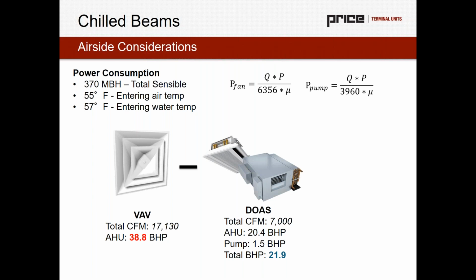When we're looking at the airside considerations for this equipment, I just want to paint it a little bit more. This is a case study that our beam team put together, looking at an open office environment providing 370 MBH of total sensible cooling with 55°F entering air and 57°F entering water. When we look at the power consumption of our fan and our pump in comparison to just the fan of a VAV system, we're generally seeing that 30% mark, but it can go up. In this case, an office example, we were seeing 44% less peak load brake horsepower. So significant energy savings, just because it's so much easier to move fluid rather than it is to move airflow through ductwork.